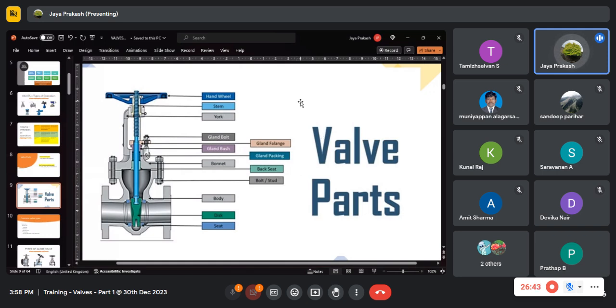Because most of you have done valve inspection, right? Anybody knows? Packing, sir, the pressure containing boundary is up to the packing area, the gland area. During the back seat test, is the pressure withstood by the packing or not? During the assembly, does that packing withstand the pressure or not?